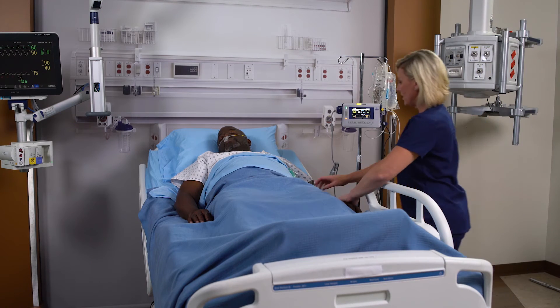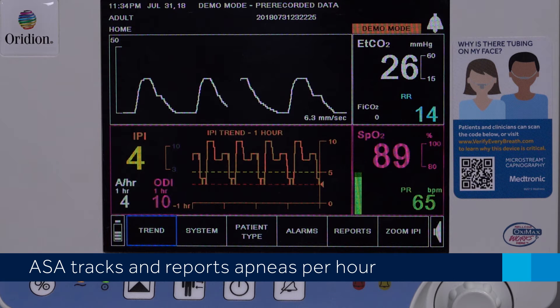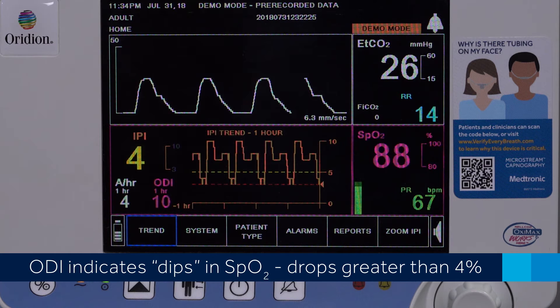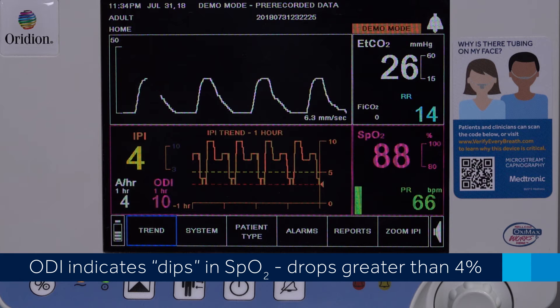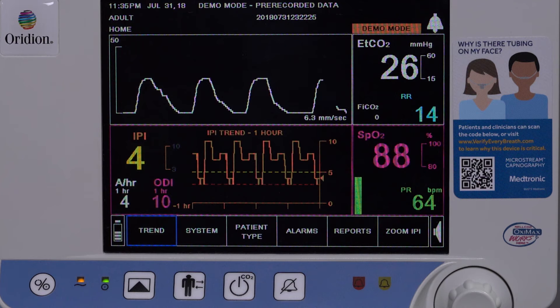Using artificial intelligence, the IPI gives clinicians early awareness of changes to a patient's breathing. The apnea sat alert algorithm, or ASA, tracks and reports apneas per hour. The oxygen desaturation index, or ODI, indicates dips in SpO2 — specifically, the number of times the SpO2 value dropped four percent or more from baseline and returned to baseline within four minutes.